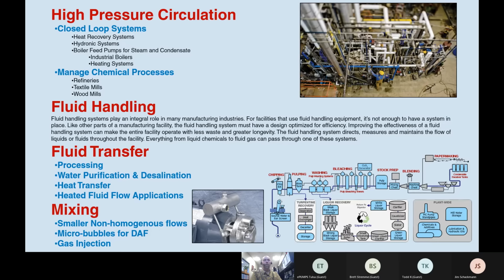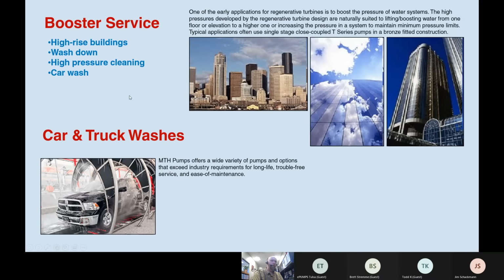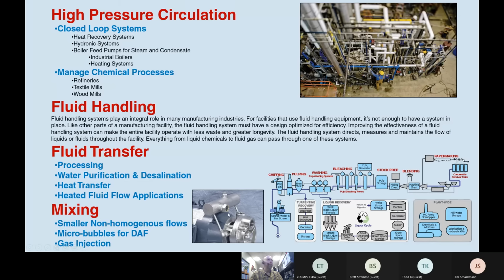I'm not going to read all this because I'm going to leave you with a copy of the PowerPoint presentation. But I will point out this picture down here. This is a seal quench gland that we use in the paper mill industry. The tank sitting above this pump is filled with oil. A chemical is pumped with a stainless steel pump, and if the fluid touches air, it crystallizes. A mechanical seal works by the fluid lubricating the seal as it seals, and crystals will build up on that seal and make it prematurely fail.